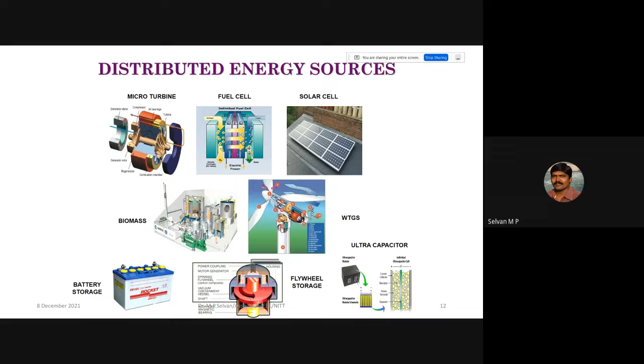I'm sorry, I have indicated only DG here. Actually, we should write this as DER, distributed energy resource. One, distributed energy resource. Two, it can be a generation or it can be an energy storage. So when this kind of embedded source is available in the system, the power flow can be in a reverse direction also. You cannot say that power will always flow in only one direction. Power flow direction in a branch may reverse. It depends upon power generation, the load available at that particular node, and if you have energy storage, the level of storage you have, right?